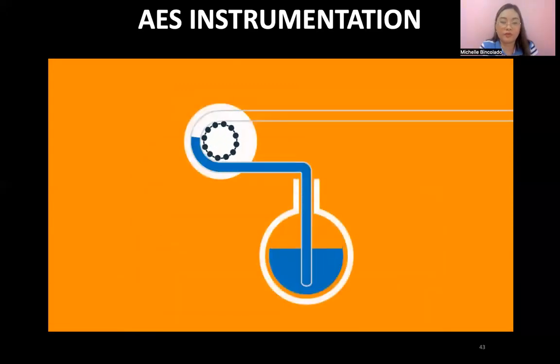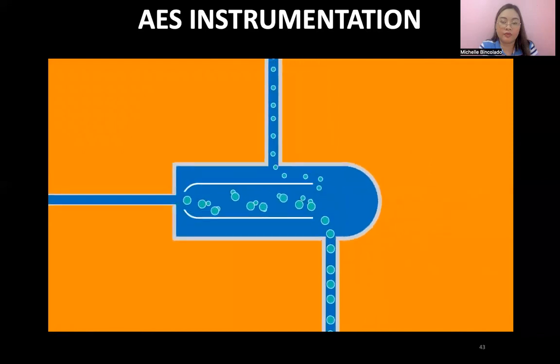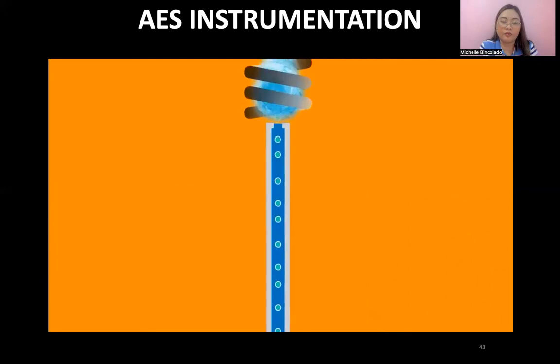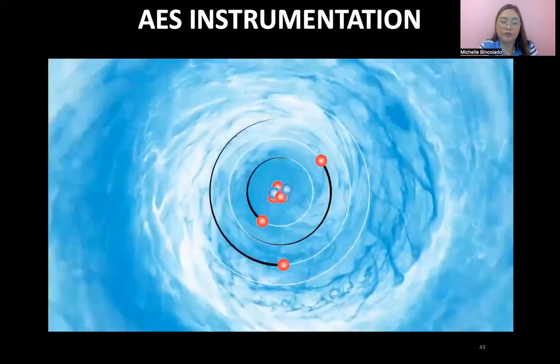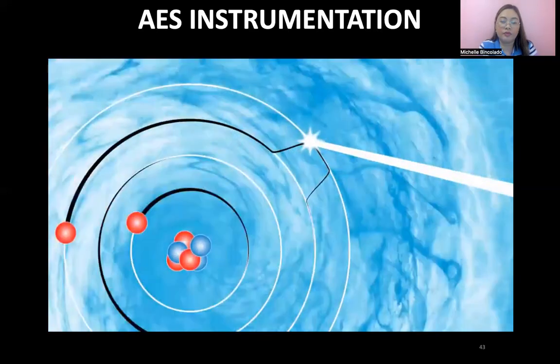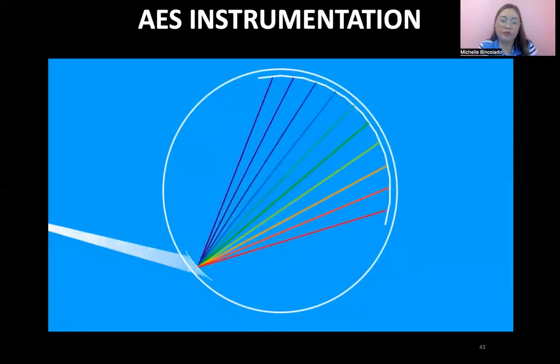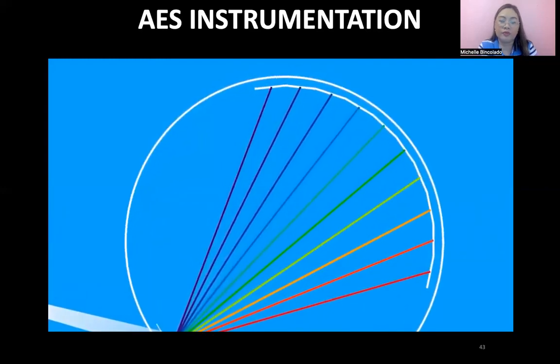The liquid sample is drawn into the peristaltic pump. In the nebulizer, it's converted into a fine aerosol spray. In the spray chamber, larger droplets drain away, but finer droplets are directed into the hot plasma. In the plasma, the sample aerosol vaporizes, and its atoms and ions are excited, so that their characteristic wavelengths are emitted. The light is transferred into the high-resolution, no-purge sealed optical system, which separates the light into the specific wavelengths for the elements to be measured.